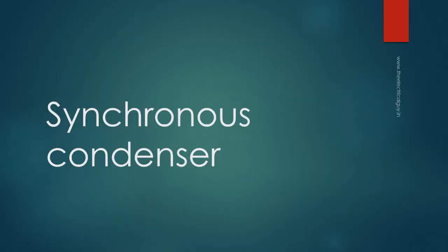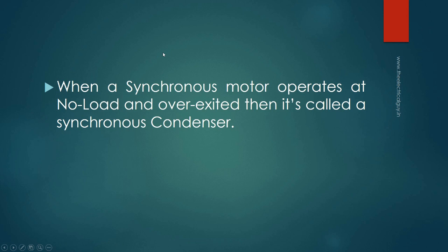When a synchronous motor operates at no load and is overexcited, it is called a synchronous condenser. When overexcited, it provides leading current and works like a capacitor. Let's see how a synchronous motor supplies reactive power.